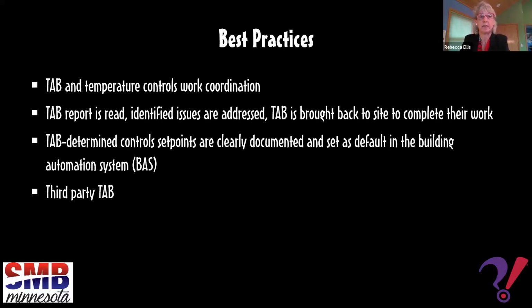Mechanical contractors and design engineers need to read the TAB reports and understand what issues were discovered that need to be corrected. You're spending good money on the TAB contractor and they're finding really good stuff. And if you don't do anything about it, it's a waste. So as commissioning professionals, we regularly see problems documented in the TAB report that no one takes responsibility for correcting. That's an issue, because that's going to come back and bite you later when they manifest themselves in problems the owner is going to discover.